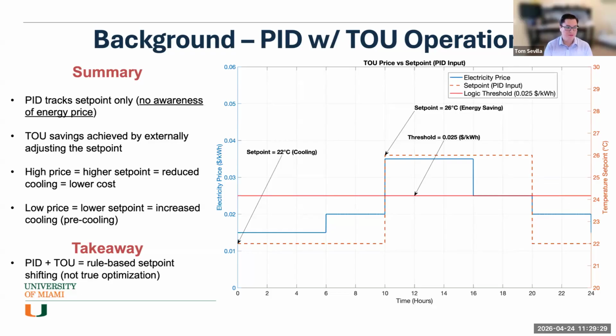On this graph, we're looking at a 24-hour period with a blue pricing line that has a couple of steps throughout the day. As the electricity price changes, we have logic thresholds telling the PID controller that once you cross a threshold, you can set a different temperature. A higher price means a higher set point, so you reduce cooling and lower cost, whereas a lower price means a lower set point and increased cooling, taking advantage of pre-cooling the building.